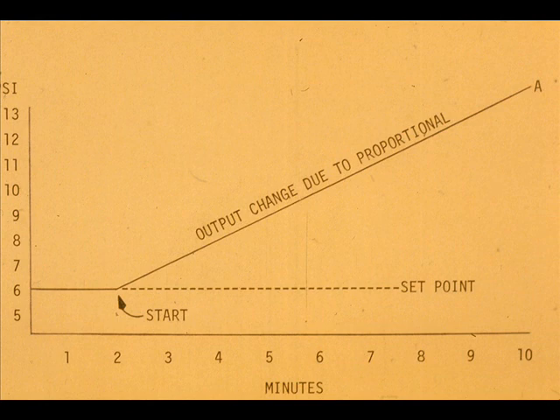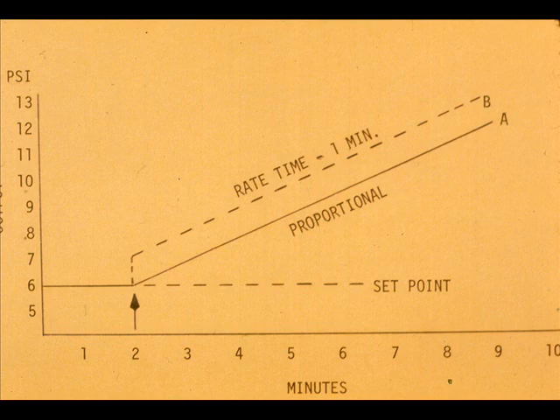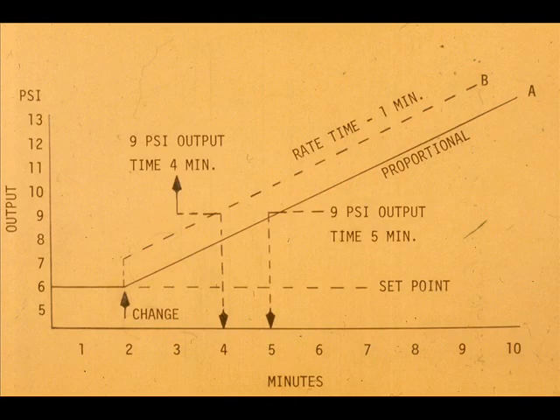Curve A represents a proportional controller output change caused by the measurement moving away from the set point at a steady rate. Curve B shows what the output would be if the controller had rate action and the rate time set at one minute. At any point along curve B, the output is advanced by one minute ahead of the proportional only output.